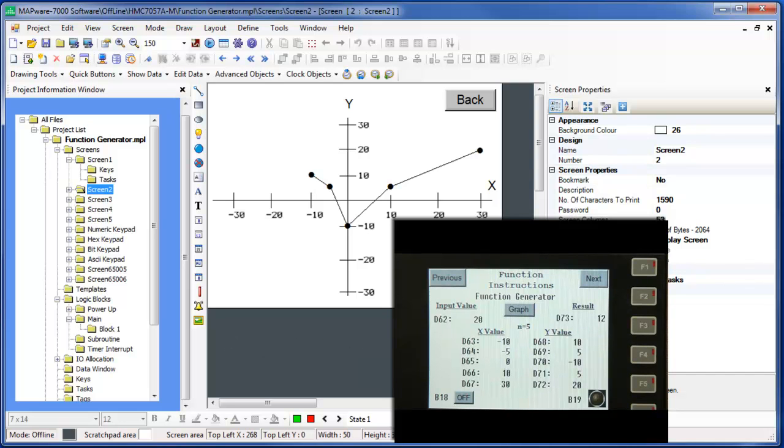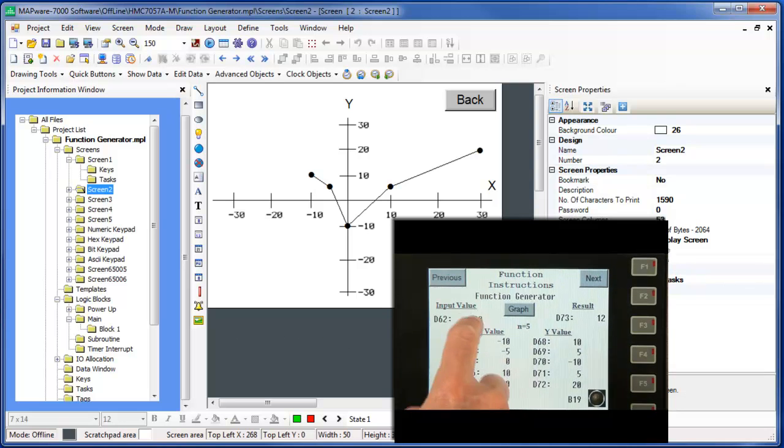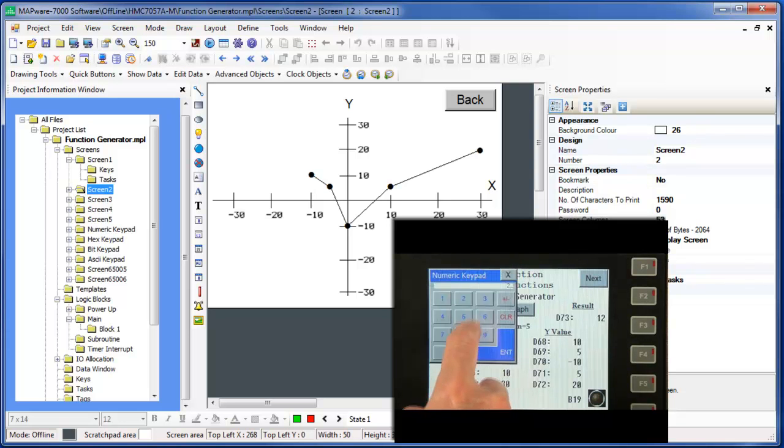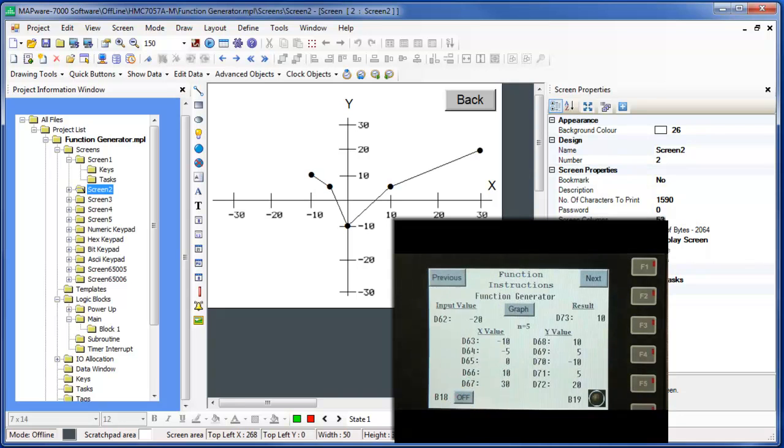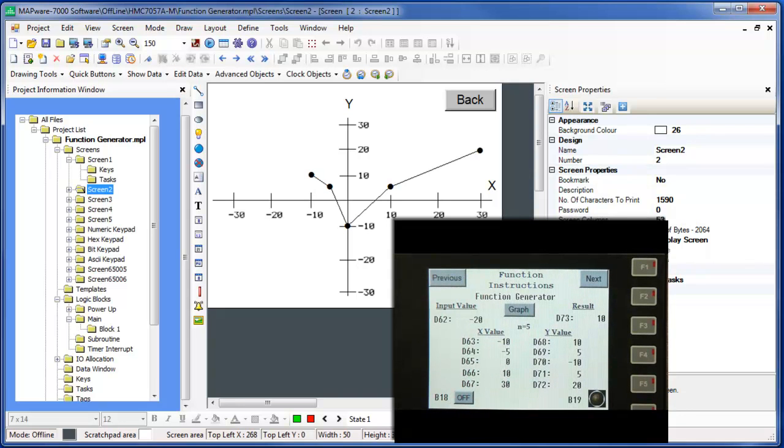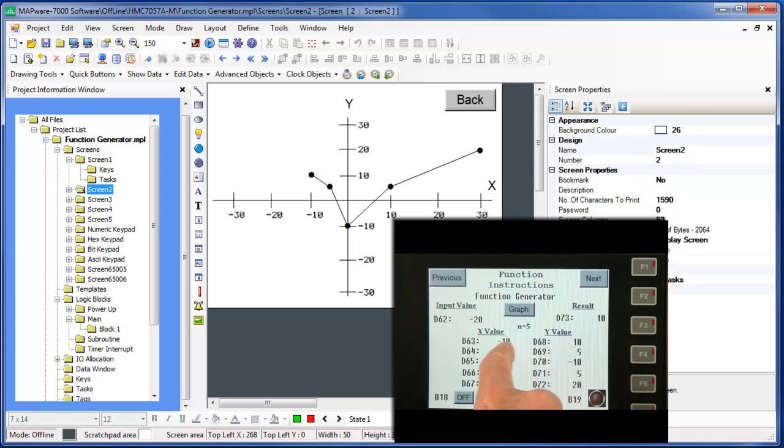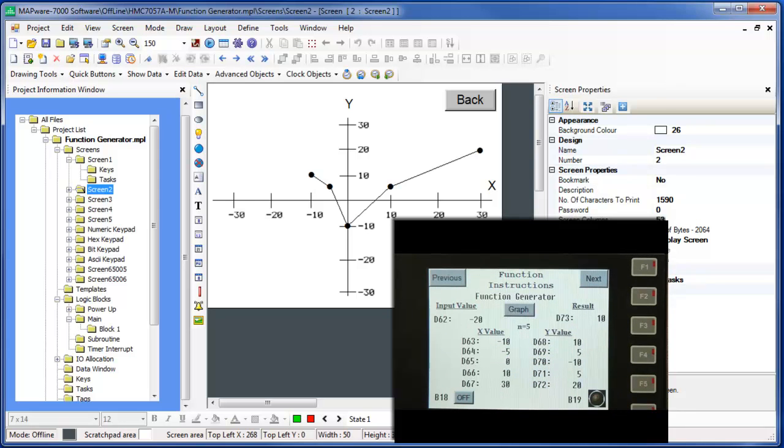What happens if we enter in an X value that is less than negative 10? When any X value that is less than the lowest X value in the data table is entered, the function generator simply uses the Y value, in this example 10, as the computed Y value entry.